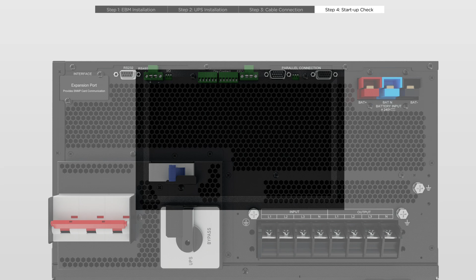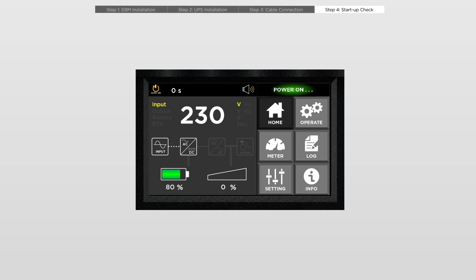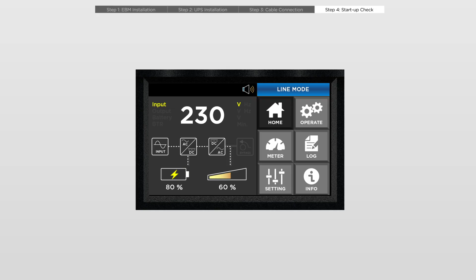Turn on the input circuit breaker and the UPS begins initializing. Select the stack mount display orientation. Complete the initial settings by configuring the parameters. The UPS will run self-tests, which may take a few minutes, then transfer to line mode when ready for use. For optional inspection, verify that the UPS switches to battery mode by turning off the UPS input circuit breaker.